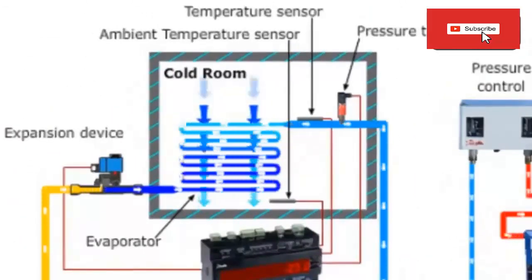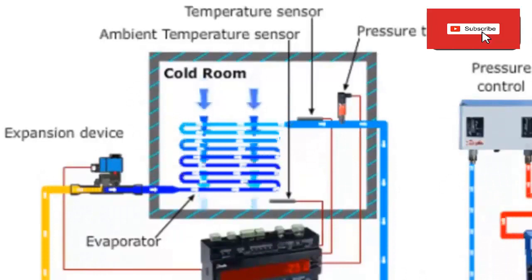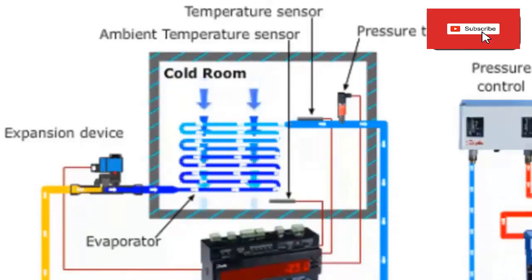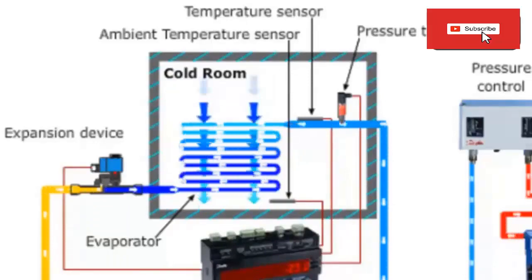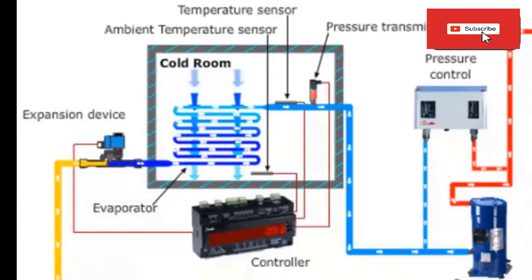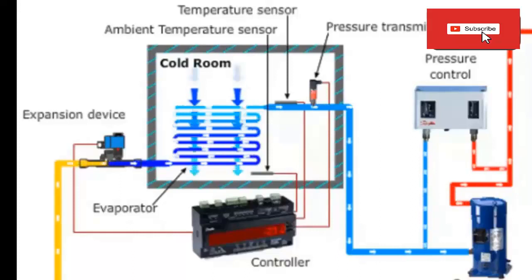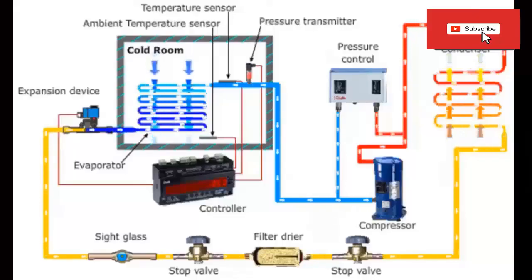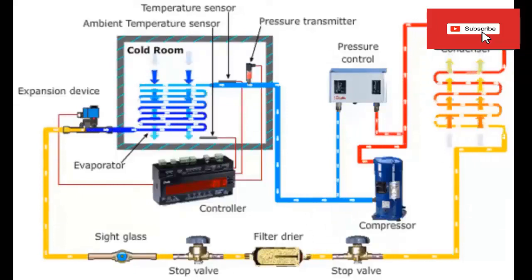The evaporator temperature sensor informs the room controller of the exact temperature of the evaporator. This sensor has an internal electrical resistance which changes its value when the temperature varies. The variation of the electrical resistance brings a change of voltage that the controller uses to know the temperature. The temperature sensor inside the cold room informs the controller of the internal temperature, through the variation of its electrical resistance with the temperature.